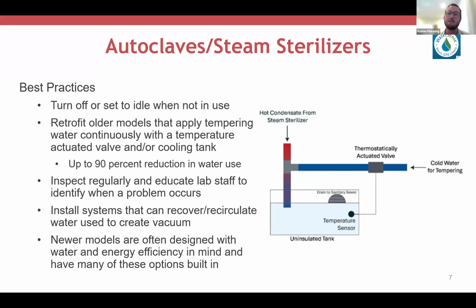Another good best practice is to retrofit older steam sterilizer models to include a temperature actuated valve and/or a cooling tank to help reduce the frequency that tempering water is applied. A system called the Water Miser is a really popular type of retrofit device. And these systems can reduce water use for tempering by up to 90%, so pretty significantly. And the diagram on this slide actually shows how this system works.